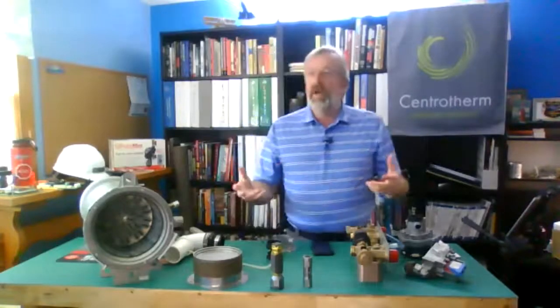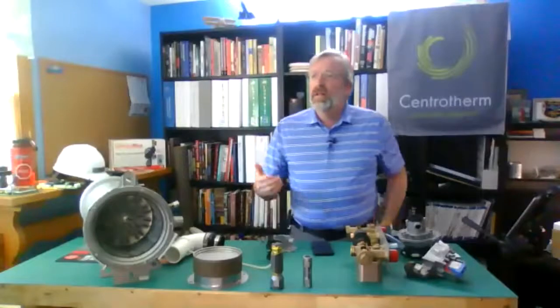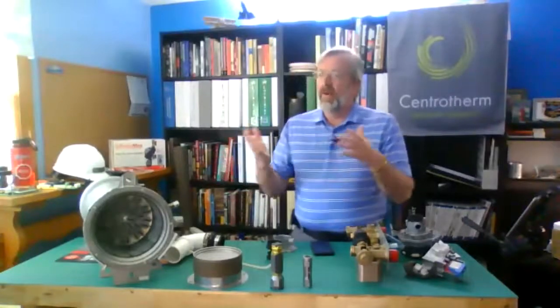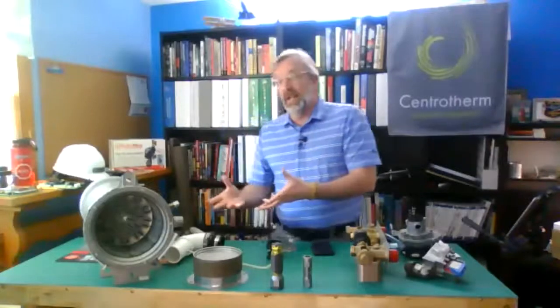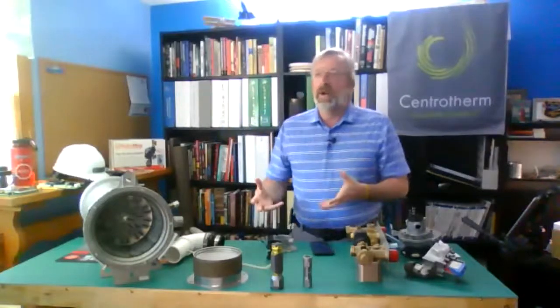Now, assuming when you installed your Noble boiler, you set up your gas valve, you did a combustion analysis, you did everything correctly. Now we want to get a couple of facts. One, how long has this boiler been installed? So if you say to the customer, hey, when did you get the boiler put in? Oh, I put it in 4 years ago. When did you service it? And they give you that look like, what do you mean? I don't have to service it. We're going to probably go right to a service. That's the direction we want to head right then. Let's save a lot of time because it doesn't take a lot of time to service one of these. And let's open it up and service it.